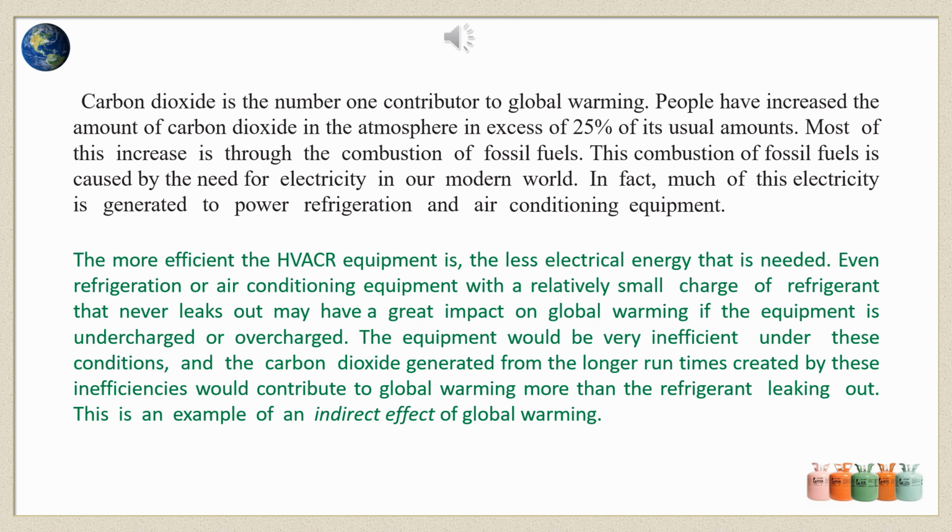Even refrigeration or air conditioning equipment with a relatively small charge of refrigerant that never leaks out may have a great impact on global warming if the equipment is undercharged or overcharged. The equipment would be very inefficient under these conditions, and the carbon dioxide generated from the longer run times created by these inefficiencies would contribute to global warming more than the refrigerant leaking out. This is an example of an indirect effect of global warming.